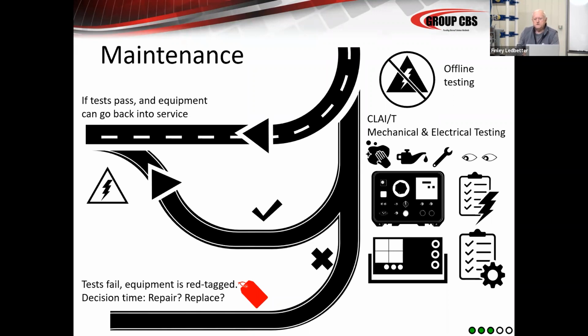So at about 1,000 operations, you need to do some pretty significant maintenance. At about 3,000 operations, in my opinion, most modern vacuum breakers need to be completely overhauled, and that's a complete mechanical overhaul with new coils, new charging motors, pawls, charging gears, springs, a lot of components. It's fairly detailed, and they are replaced with a proper replacement breaker. And we'll get into that in the next segment.